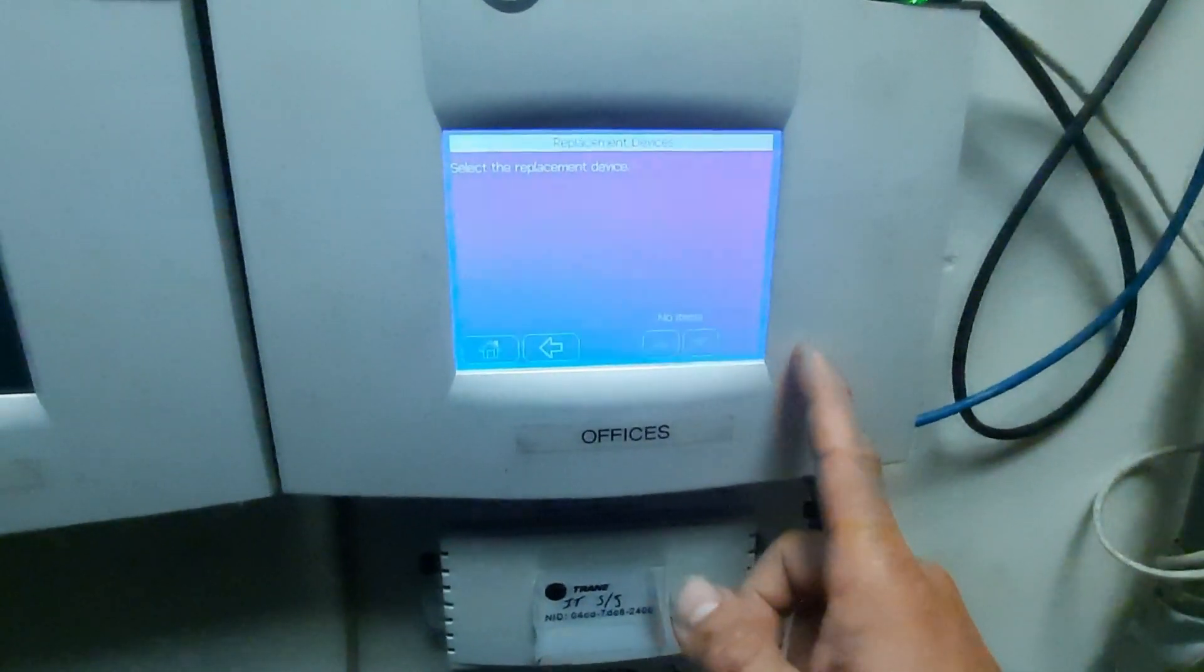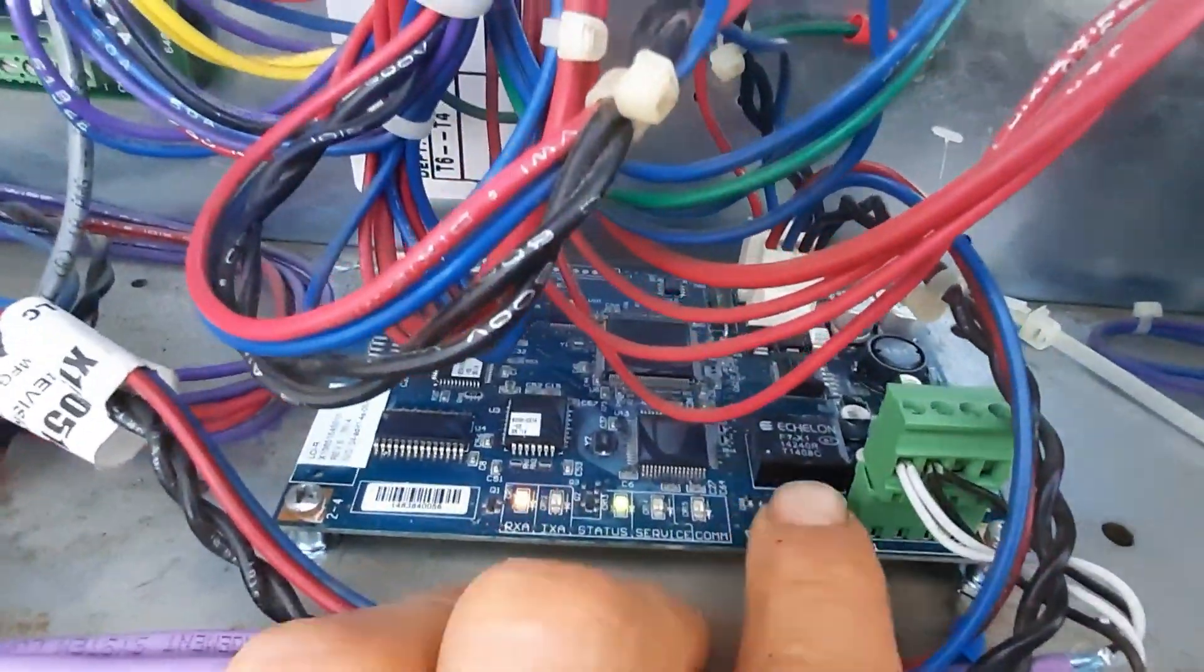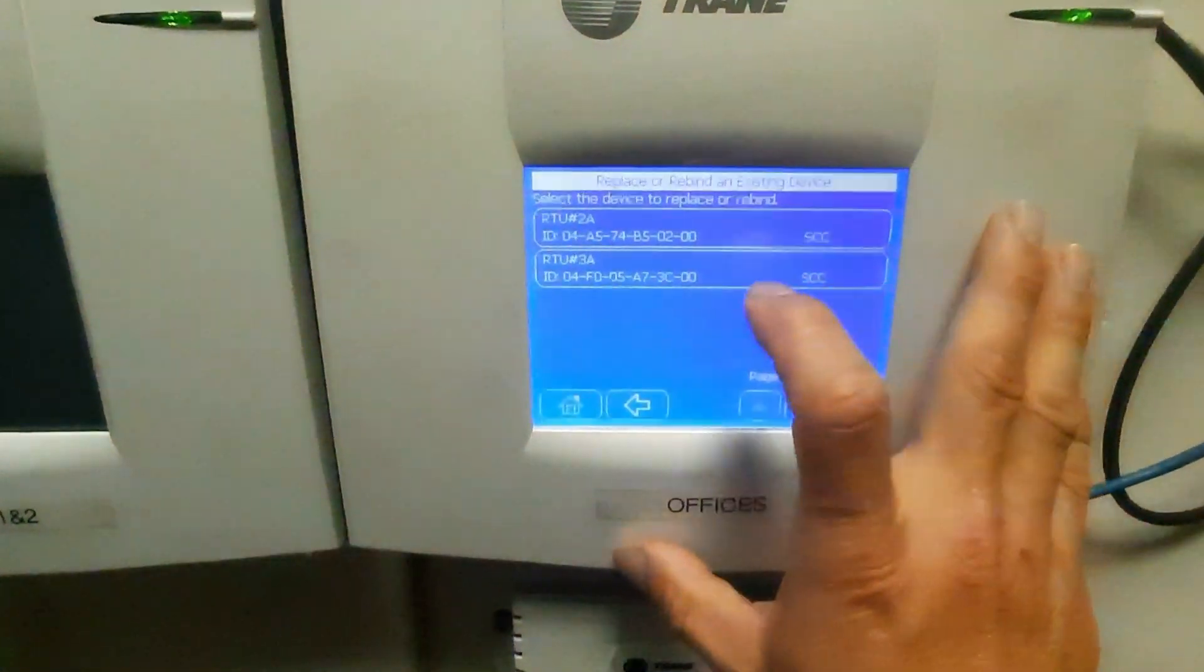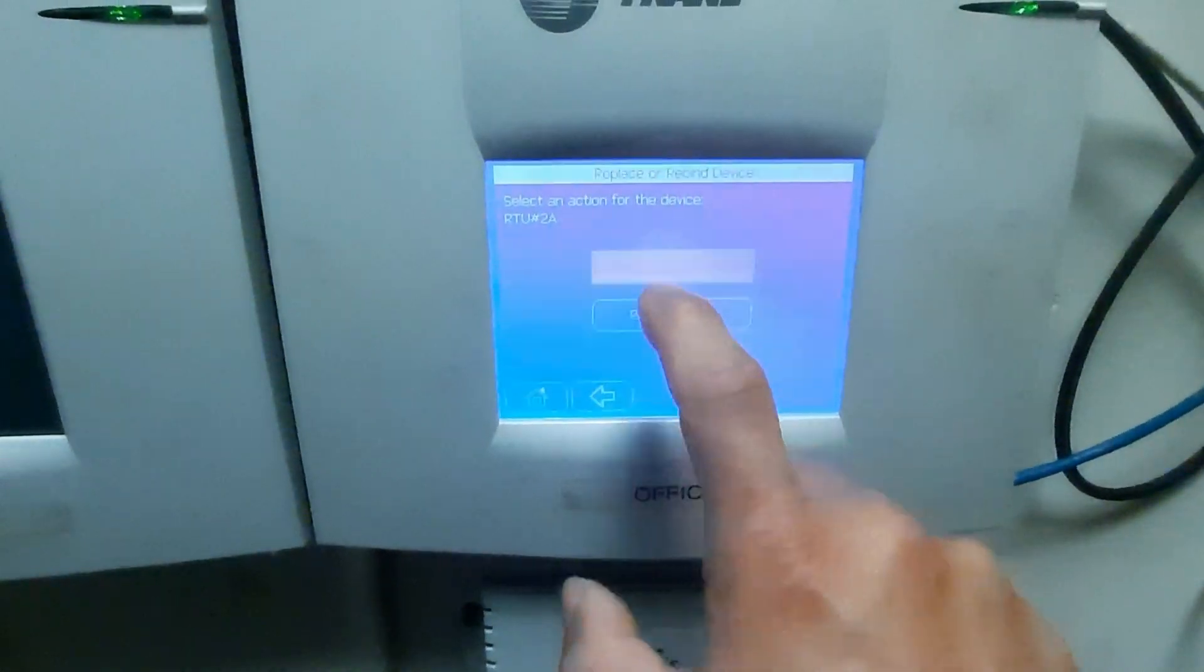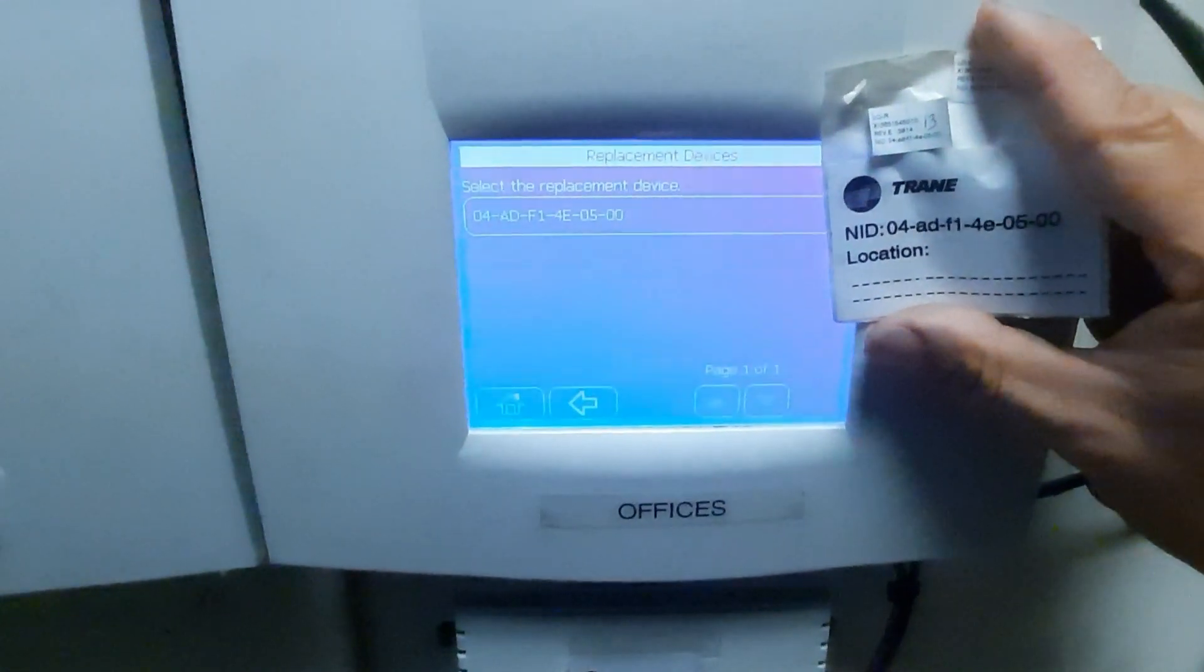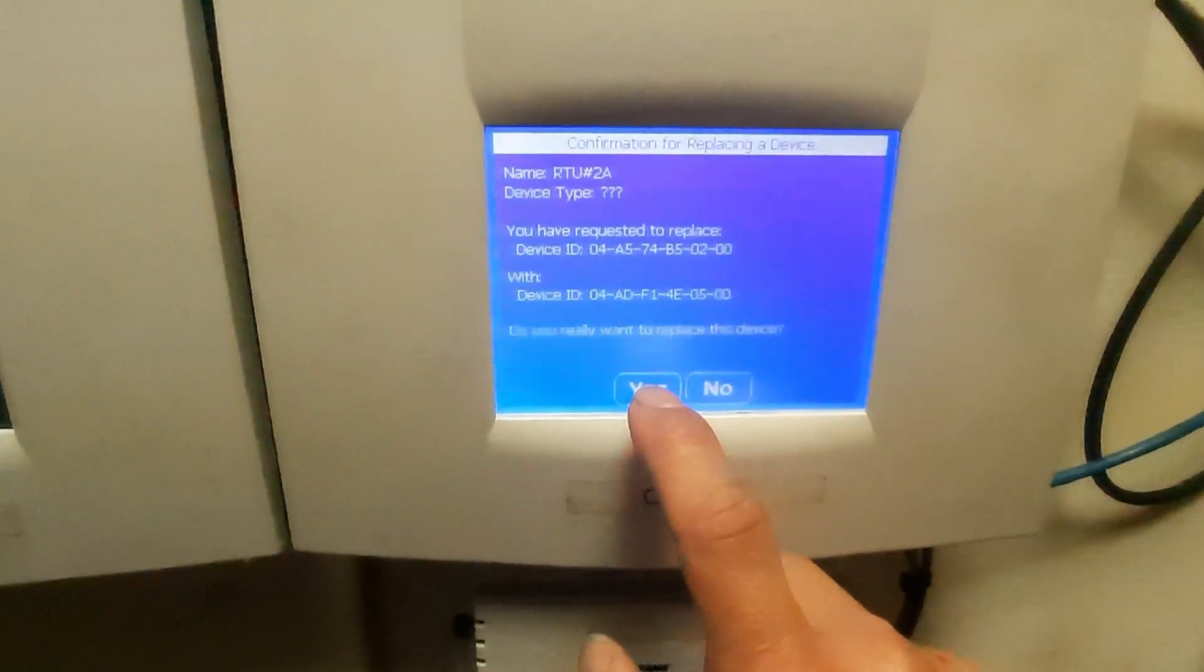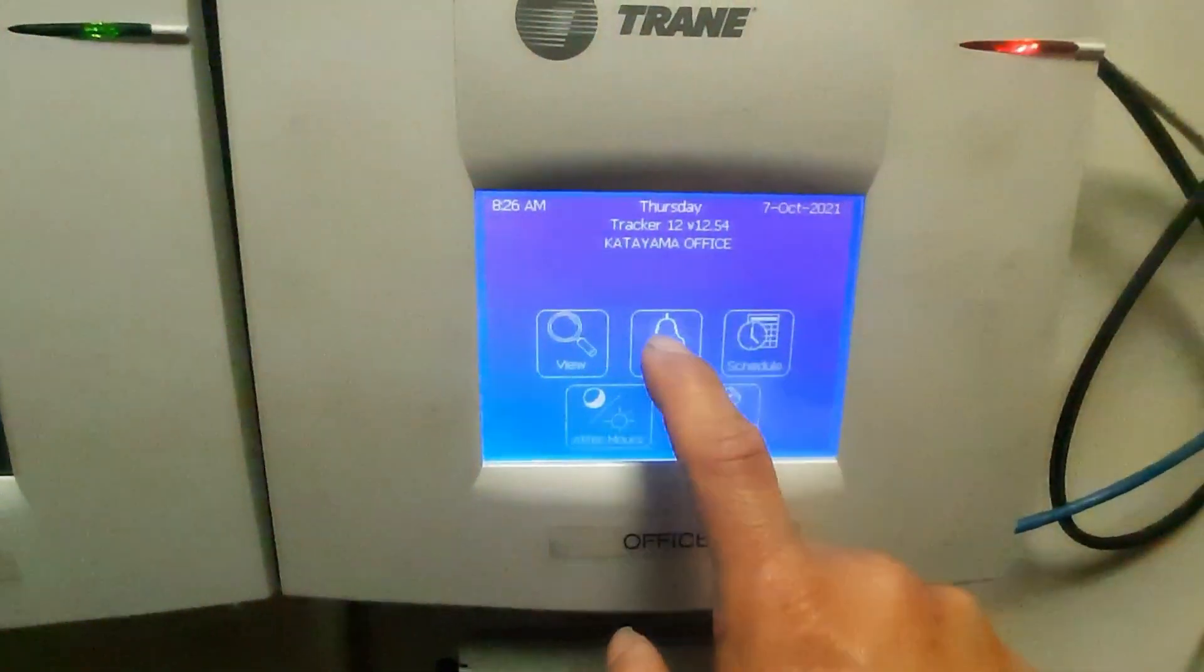I'm not seeing it yet. Let's go up and hit my service pin and see if it pulls that device up. Service pin. Service light's gonna come on just a couple seconds. All right, so one more shot here. Replace/rebind existing device. We're back at the same spot. We hit our service pin, so we should have it. If we go to replace device, that's gonna be my replacement device. Do you really want to replace this device? Yes, I didn't come this far not to replace it. And boom! We do show an alarm. Let's go back and see what that alarm shows us.